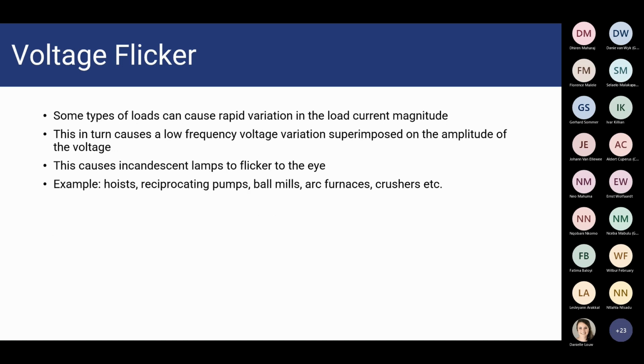Okay, so what can cause flicker, or how is flicker introduced? Some types of loads can cause a rapid variation in your load current magnitude. This in turn causes a low frequency voltage variation superimposed on the amplitude of the voltage, and this will lead incandescent lamps to flicker to the eye. Some examples of loads that commonly introduce voltage flicker are reciprocating pumps, ball mills, arc furnaces, and crushers, because of the rapid variation in the load current that they draw.